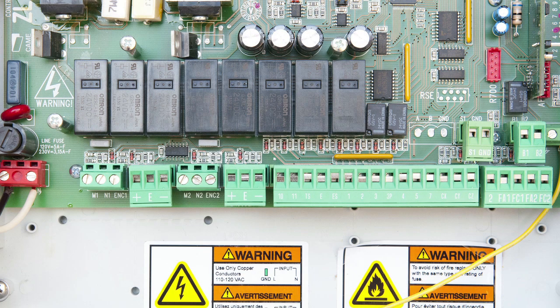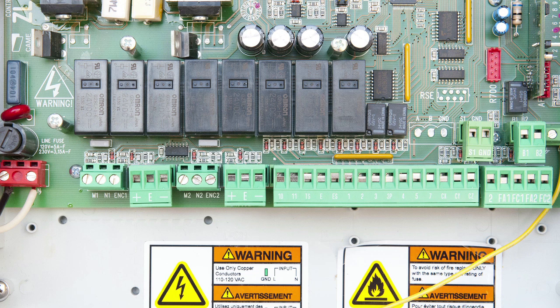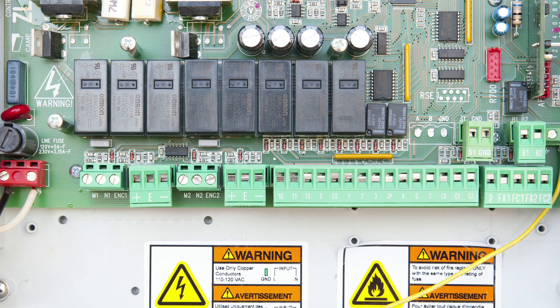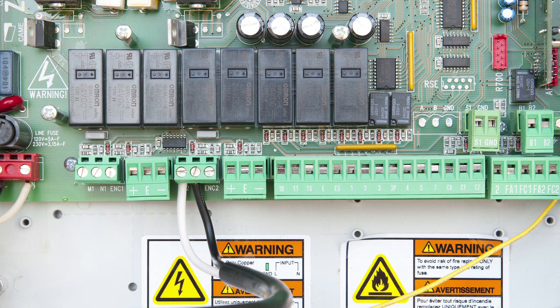To wire the gear motor power, connect the black and white wires to the N2 and M2 terminals on the control board. This is for a right-hand configuration. For a left-hand configuration, simply reverse the wires.